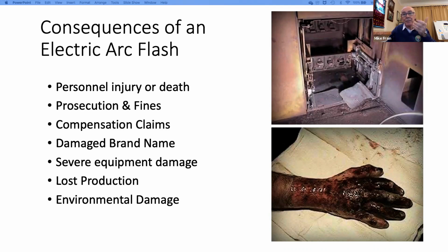Then there's the losses from severe equipment damage and lost production. That can be eye-watering. There can be big figures that never really seem to be taken into account properly. Again, for the next one, environmental damage, I can hear eyebrows being raised. Well, where does environmental damage come from in an arc flash incident? I'll just refer you to something that happened to me. I got called out on one very wet Sunday night in August 1992. I know it's a long time ago, but the fire brigade were just dampening down what remained of their main substation when I discovered that the cause of the fire was an arc flash in a PCB filled high voltage capacitor. Polychlorinated biphenyls, by the way.